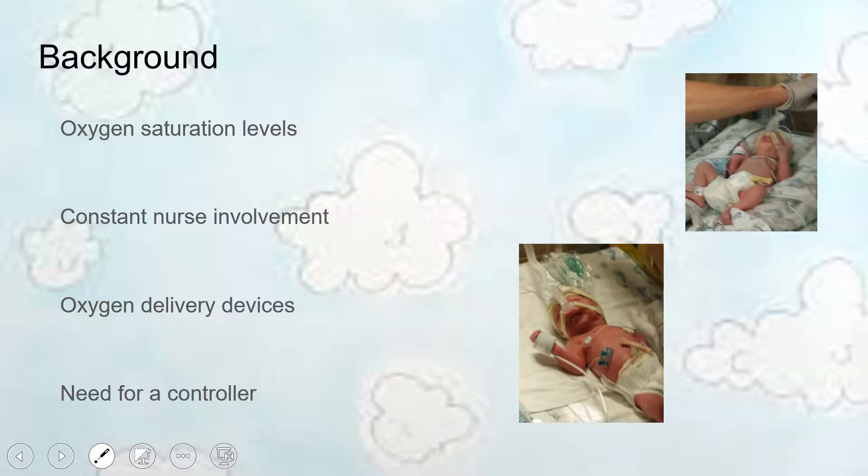Ideal levels, 90 to 98 percent, but if they ever fell outside of that range, there'd be an alarm, and how they'd adjust it is they'd just simply adjust a knob that would change basically the concentration of oxygen coming into the baby.